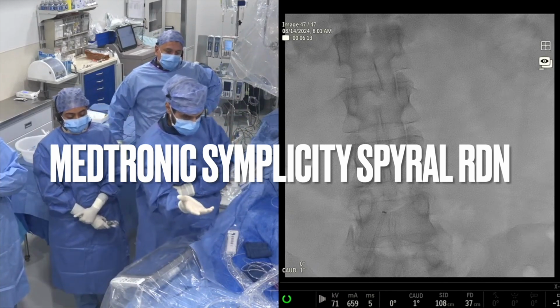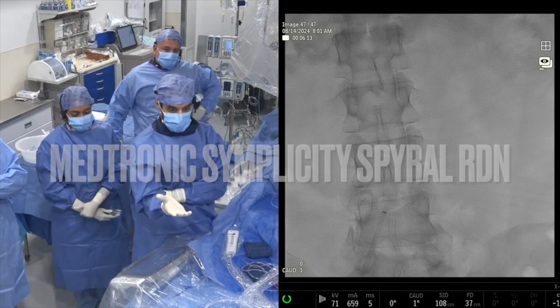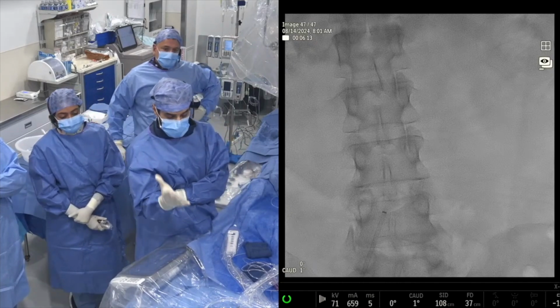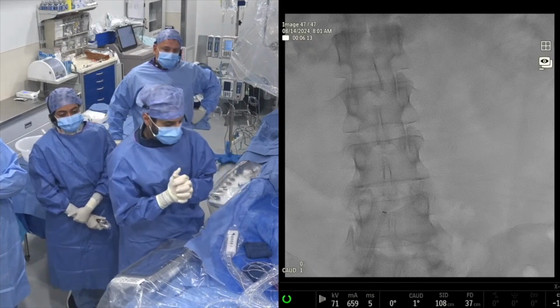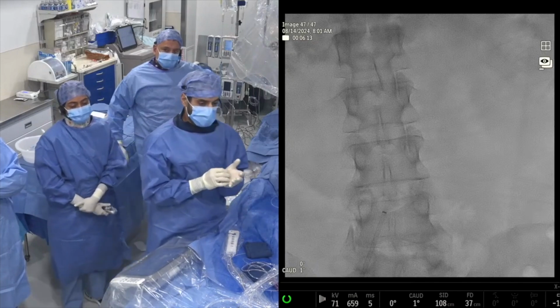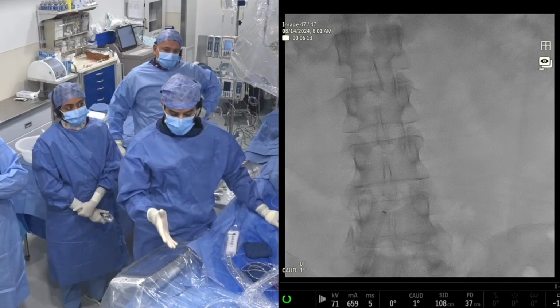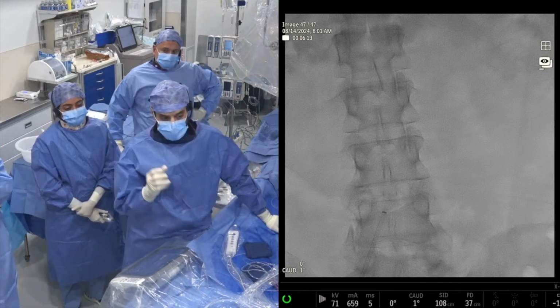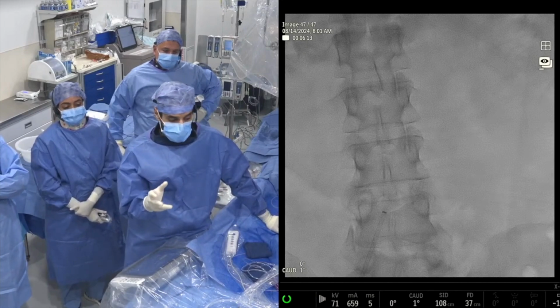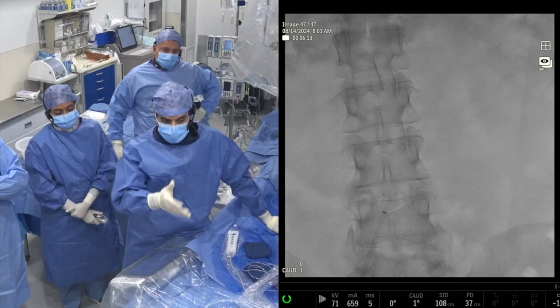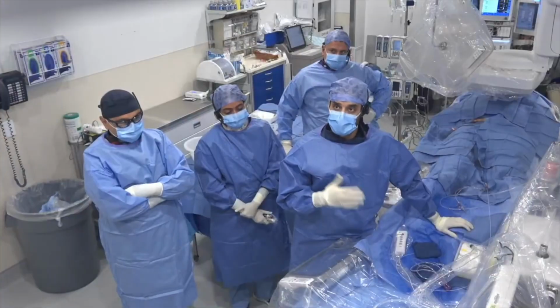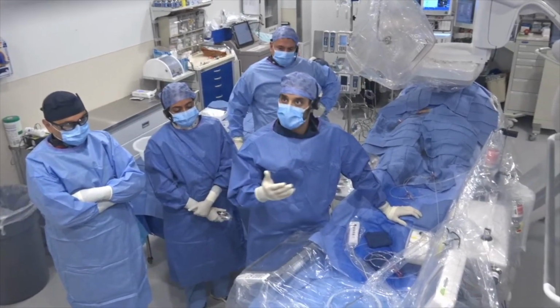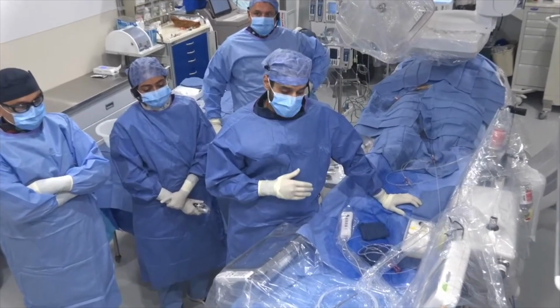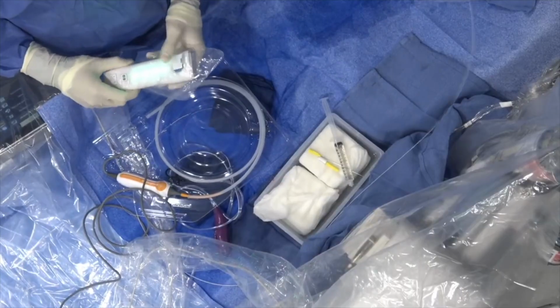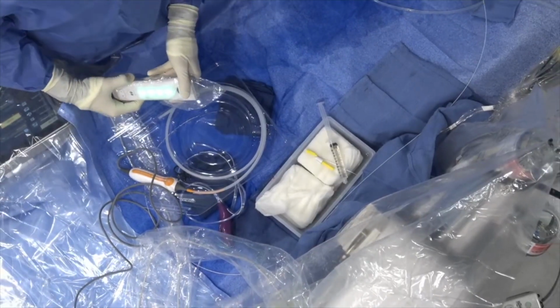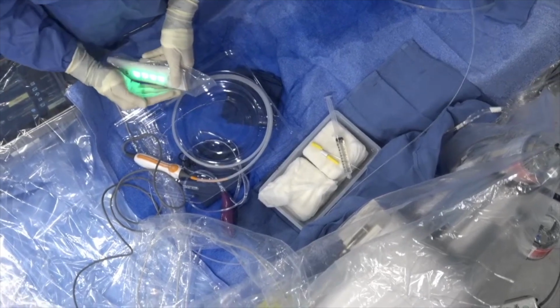Back plug, which ends up going to the Medtronic Symplicity generator. The generator itself has a few separate components to it. One includes the insertion port for the catheter itself. There is a ground pad that also has to be put on the actual ground, and it's its own separate plug. Important, because without this you won't really be able to generate the current you need to actually create the full denervation effect. And we have here, you can't see too well because of the lights, but these 4 lights here, now you can see them a little bit better.